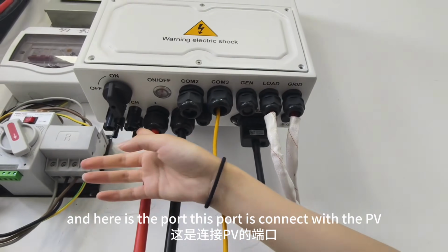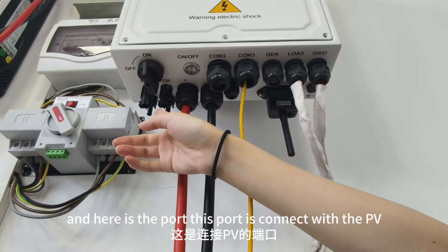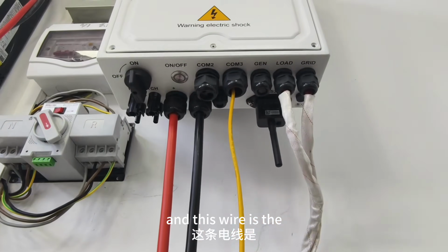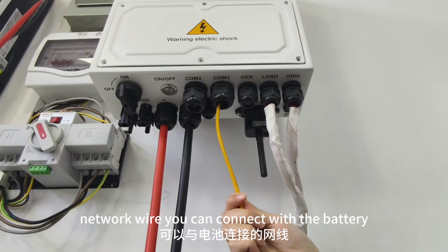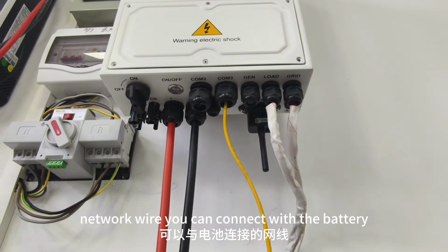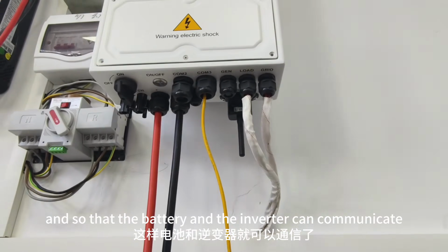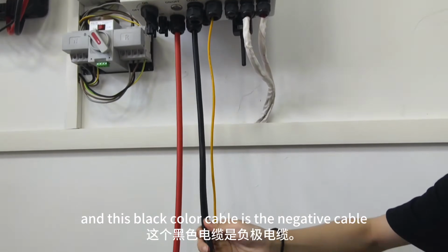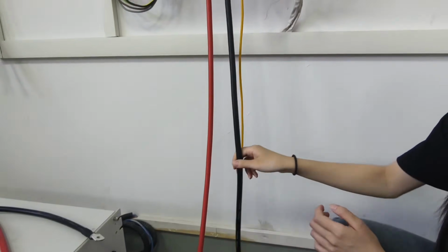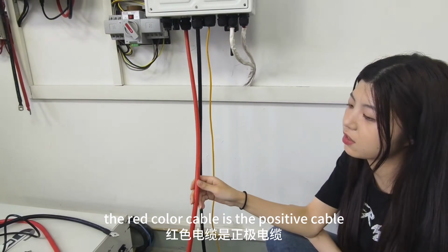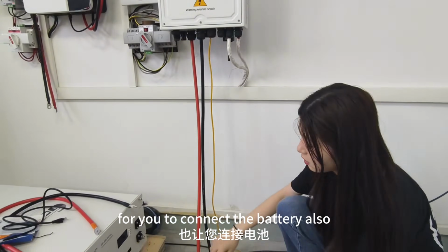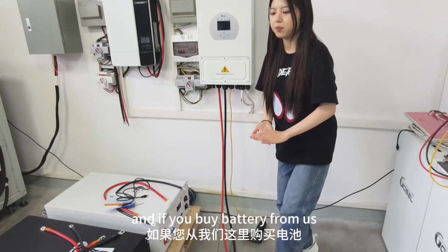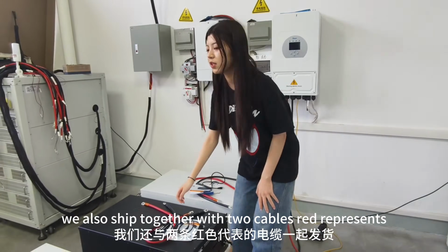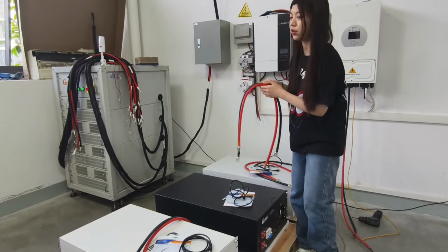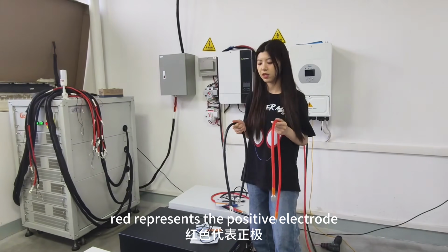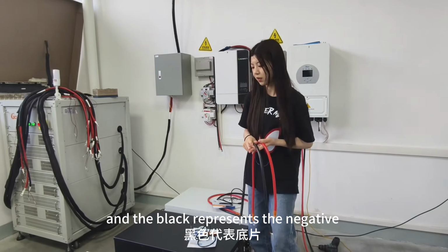Here is the port that connects with the PV, and this wire is the network wire. You can connect it with the battery so the battery and the inverter can communicate. This black cable is the negative cable, and the red cable is the positive cable, used to connect the battery. If you buy a battery from us, we also ship two cables together - red represents positive, black represents negative.